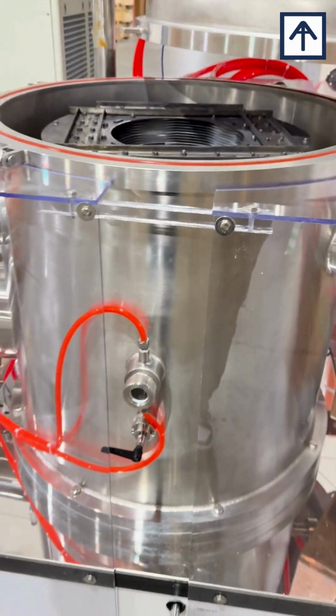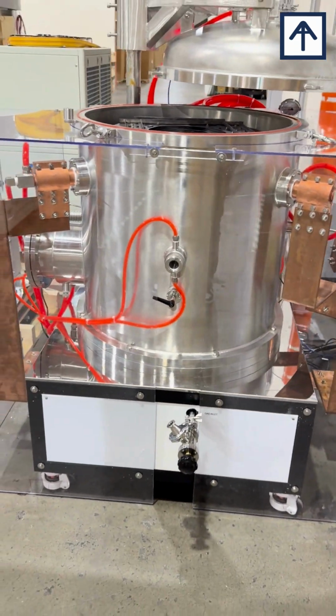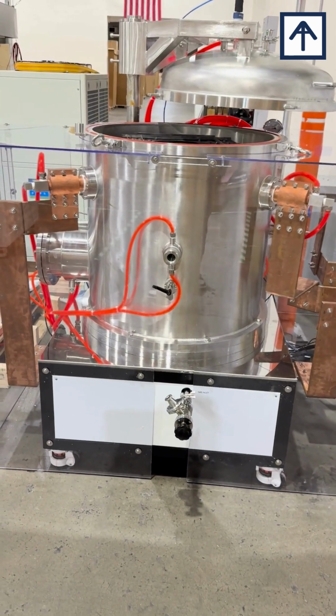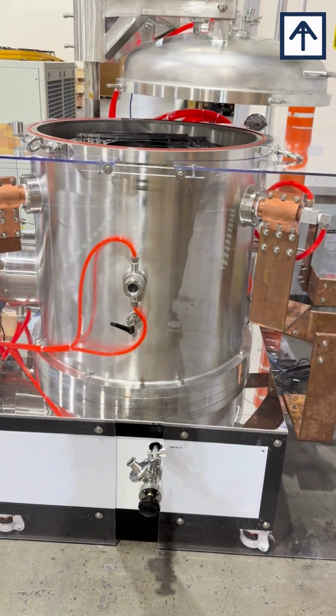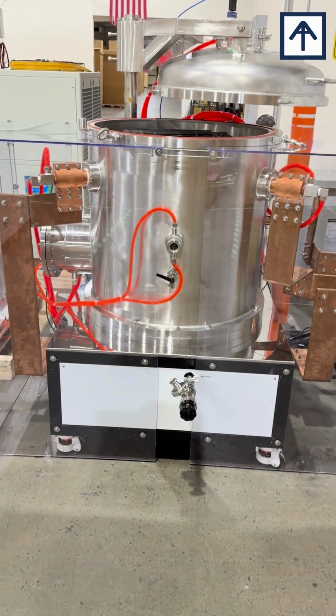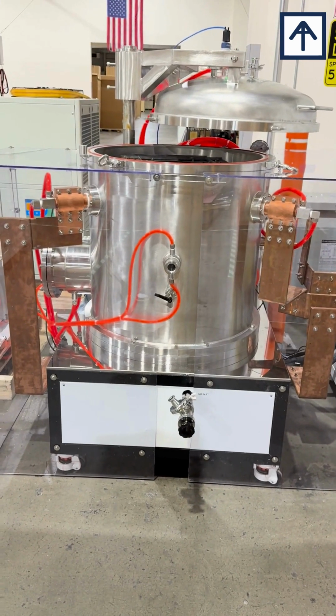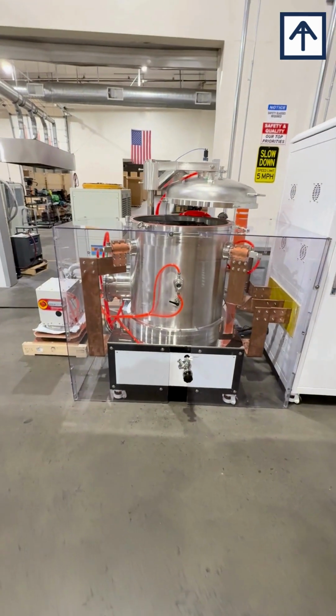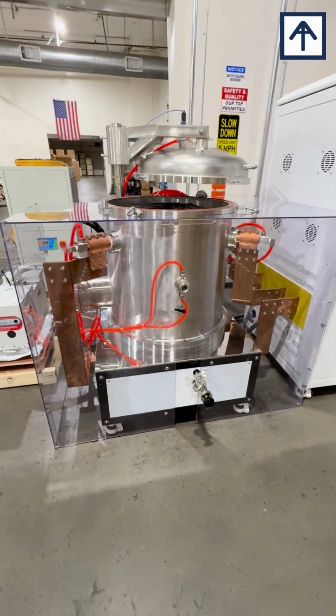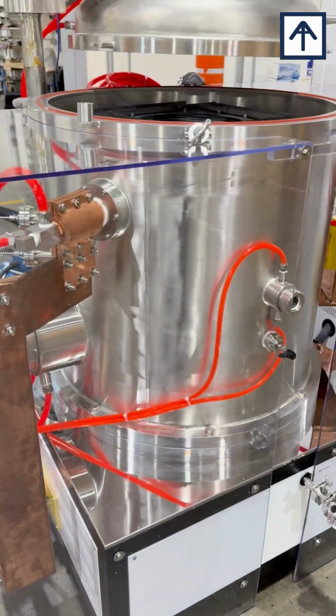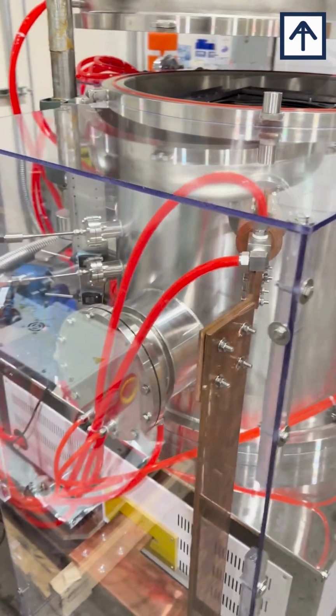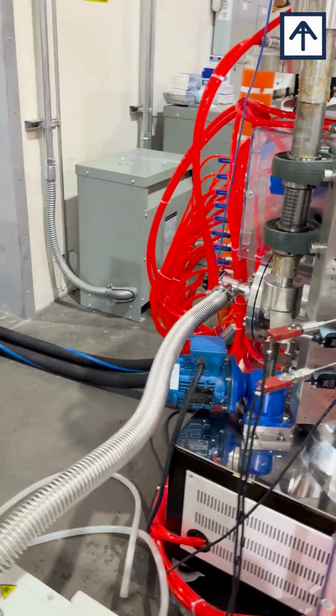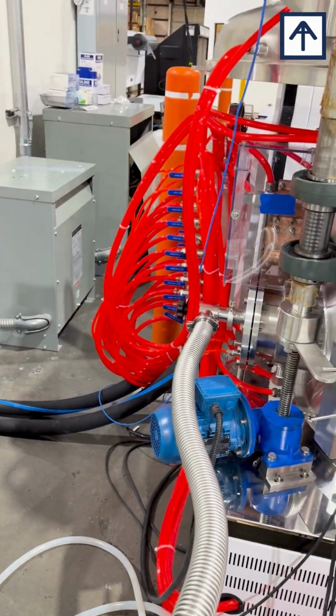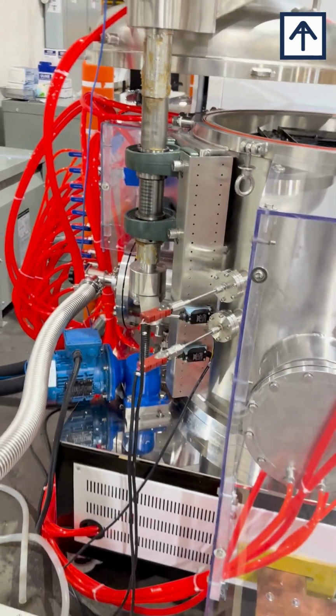The VTSF comes with a water-cooled body for safety, which is regulated at temperatures of 10 to 35 C with the help of the chiller. The size of the chiller will vary depending on the size of the chamber requested. The tube either comes with standard silicone or PTFE tube. And these are all the orange tubes that you see on the unit. This is the standard silicone tubing, and it goes all the way to the manifold, which activates your pressure sensor for the water and cooling the jacket as well.